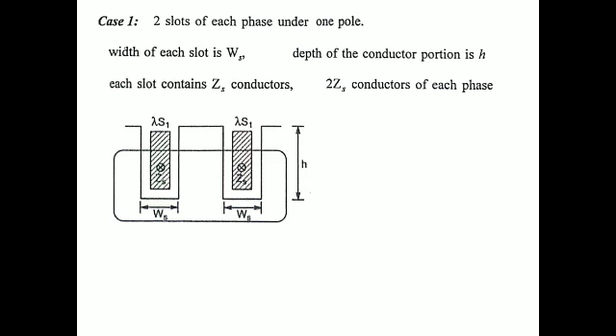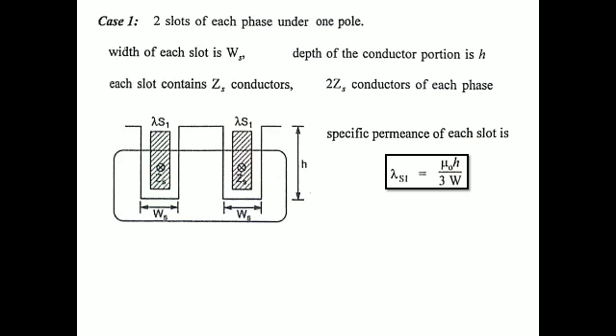In the diagram, one pole is formed by two slots. Ws represents the slot width for the two slots, H represents the depth of the two slots, Zs is the slot conductors, and 2·Zs is the value per phase. One more parameter is lambda — the specific permeance of each slot. Permeance is the inverse of reluctance; here it is declared as lambda (previously denoted as P). Lambda_s1 = μ₀·H / (3·Ws).